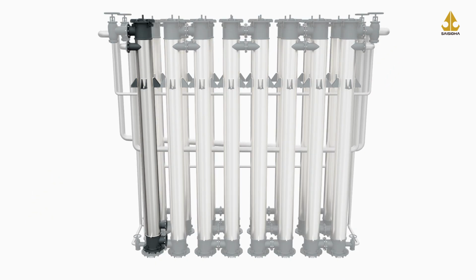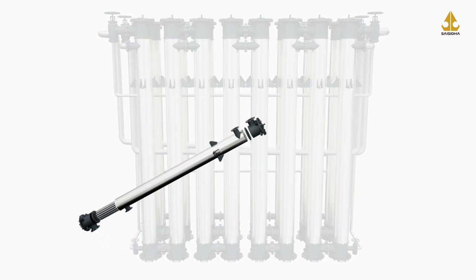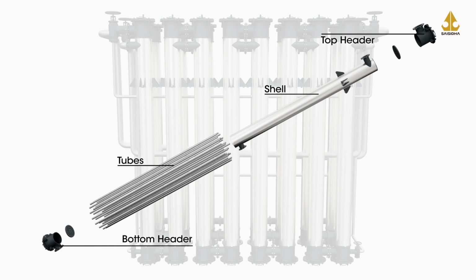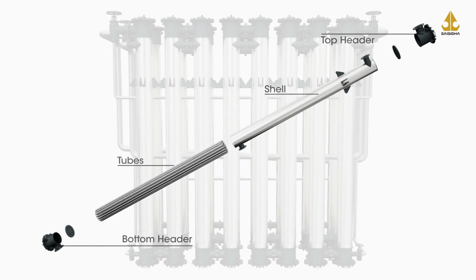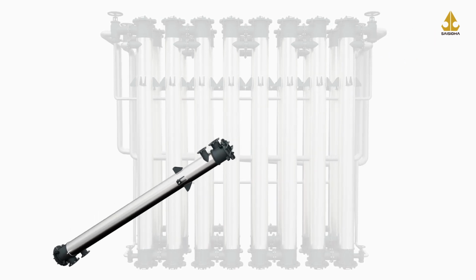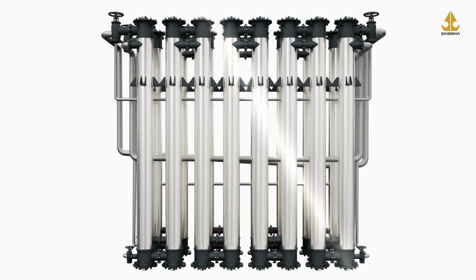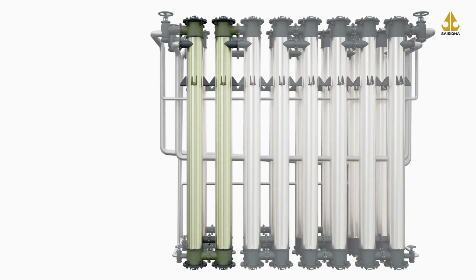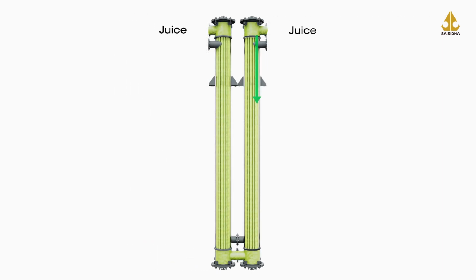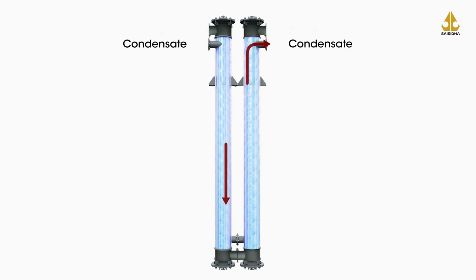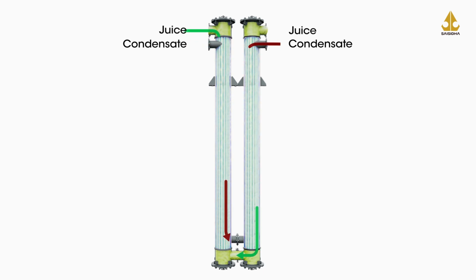Let's take a closer look. The key feature of this system is the combination of extracting sensible heat from processed condensate and recovering condensate flash to maximize energy savings. At its core, vapor condensates are used after flashing to preheat raw juice from 45 degrees centigrade to 72 degrees centigrade, enabling precise temperature control and eliminating the need for medium pressure steam.